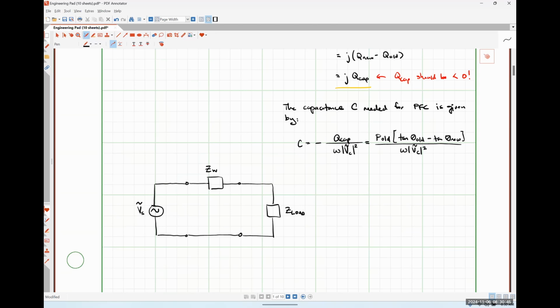One option would be to place our capacitance directly in parallel with our load. So if we have a system with a motor or something simple like that, which is an inductive motor operating at a lagging power factor just by its nature, since it's an inductive load, we could put a capacitor in parallel.